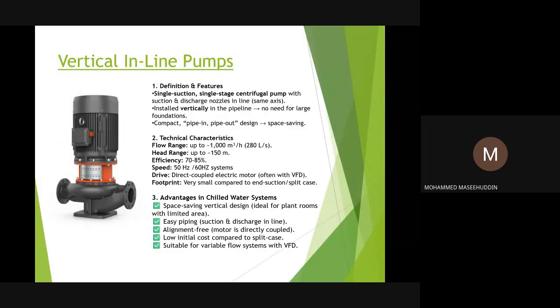And the second type of pump which we have seen in our last slides is the vertical inline pump. Basically, as I told in the last slides, these pumps are used when there is a restriction of space at the project site, and it also has economical pricing, because you don't need an inertia base, foundation, or concrete base, because it's already a close coupled pump, and there is a mounting at the bottom of the pump itself, where you can just secure it to the ground, and with bolts and nuts you can easily install these pumps.